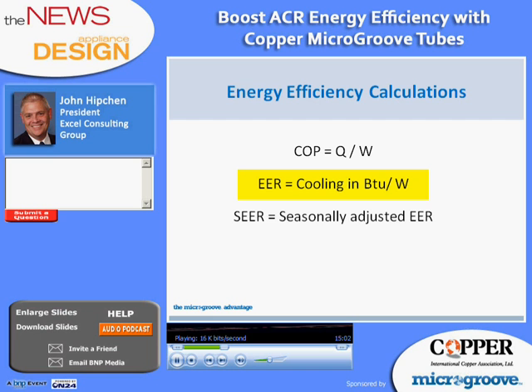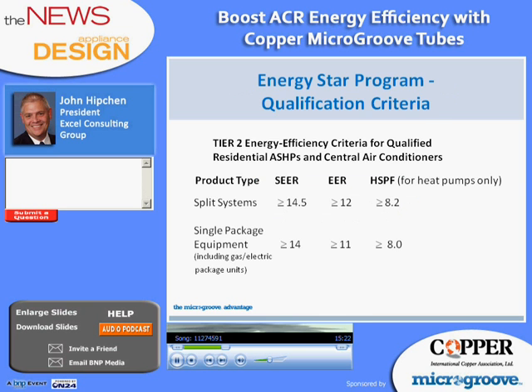The SEER rating is the same measurement, but it's adjusted to show energy consumption over a typical year of system cooling. EER, on the other hand, covers a single cycle or even a specific point in the system's operation.